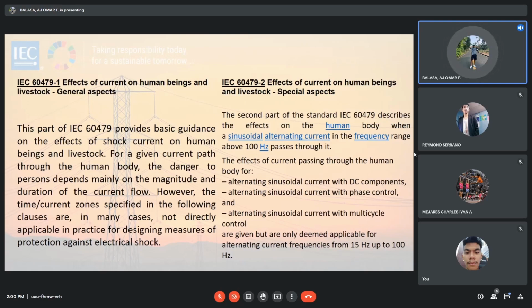The necessary information is the admissible limit of touch voltage, for example the product of the current through the body, called touch current, and the body impedance. As a function of time, the relationship between current and voltage is not linear because the impedance of the human body varies with the touch voltage, and the data on this relationship is therefore required.